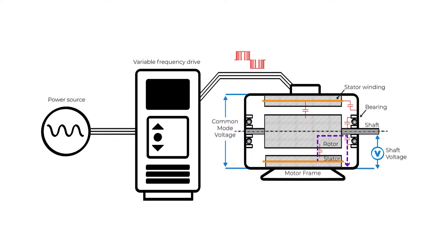Common mode voltage generates an electric charge stored in the parasitic capacitance between the rotor and the stator. When this charge gets high enough, it breaks the dielectric insulation and is discharged through the insulation of the bearing.